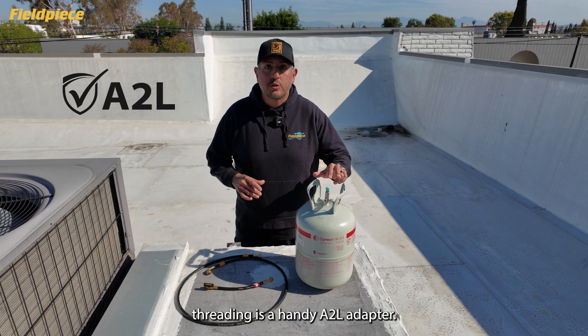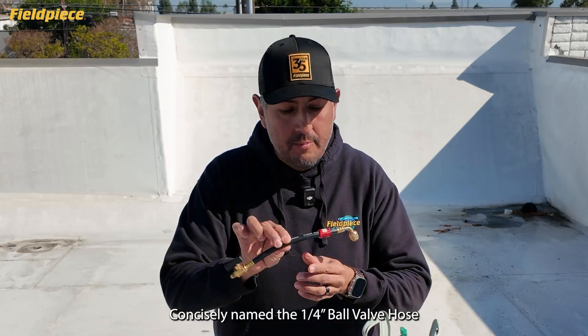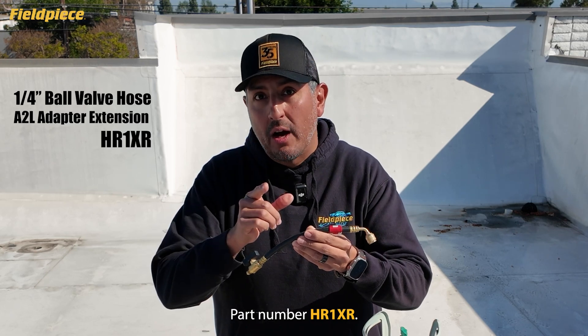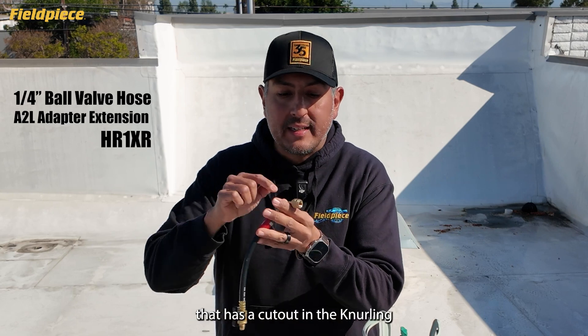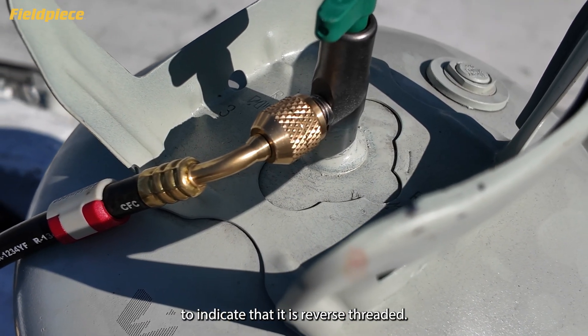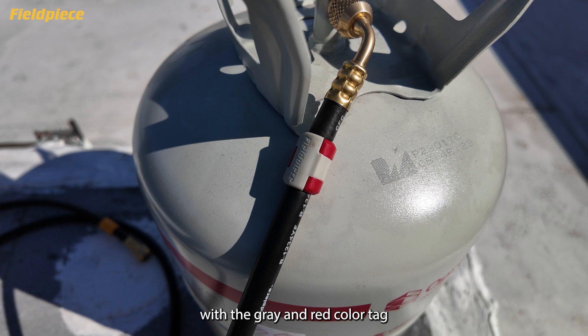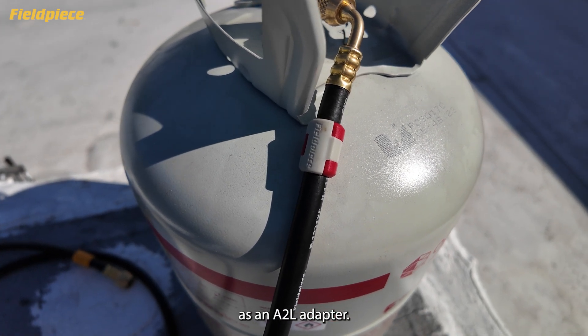Fieldpiece's solution to the reverse threading is a handy A2L adapter, concisely named the quarter-inch ball valve hose A2L adapter extension, part number HR1XR. The HR1XR has a female fitting with a cutout in the knurling to indicate that it is reverse threaded, a standard male threaded fitting on the other end, a ball valve, and comes pre-installed with a gray and red color tag to help identify itself as an A2L adapter.